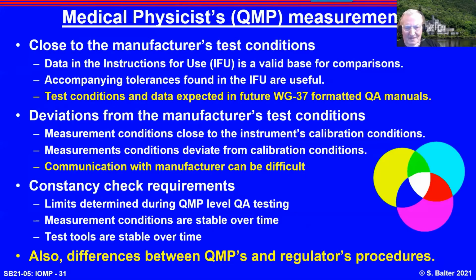Enter the medical physicist to do testing. And here's where the IEC is concerned. If the physicist tests close to the manufacturer's test conditions, data in the instructions for use is valid to see, does my installed system meet the specifications, including the tolerances. Trying to do this in a way that doesn't mean you use a very specific instrument is of great concern in our working group. Physicists commonly test in manners that are not close to the manufacturer's test conditions.